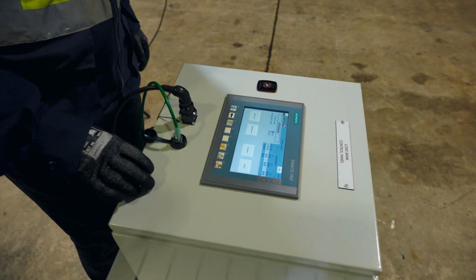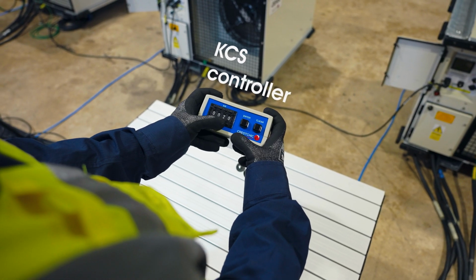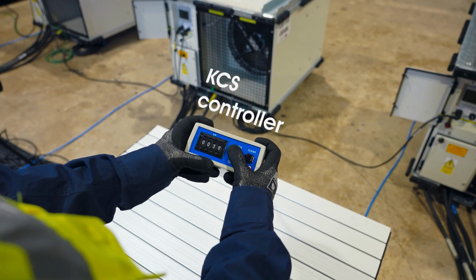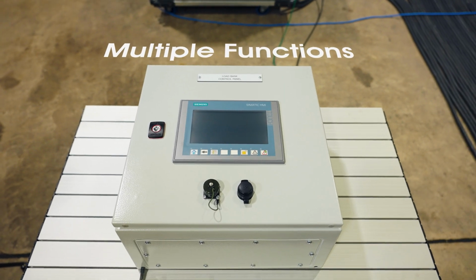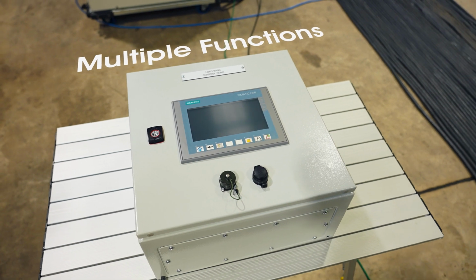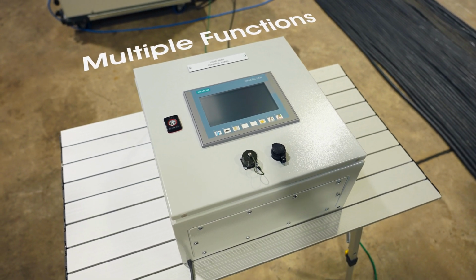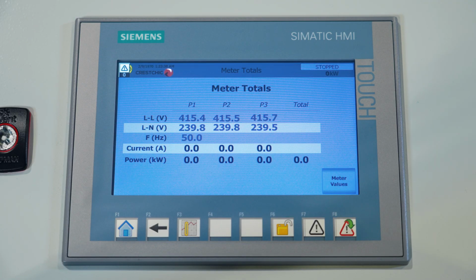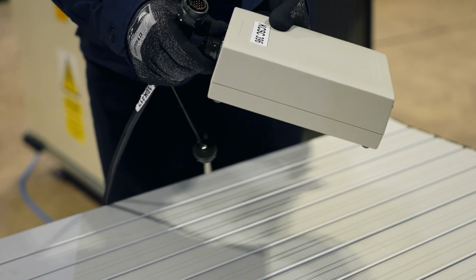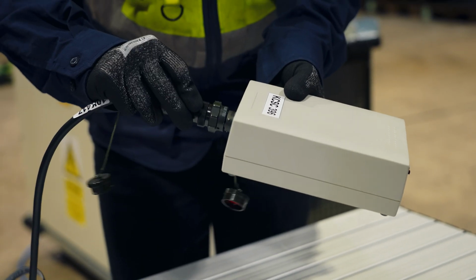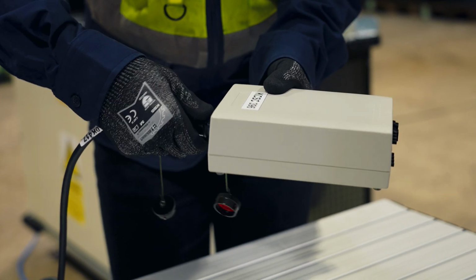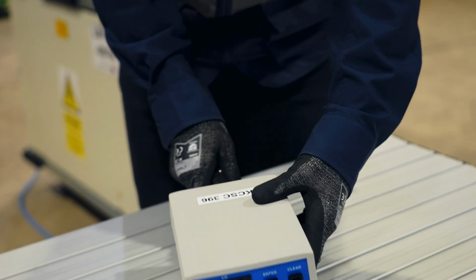Depending on the application the load banks are being used in, will depend on which controller is best suited for controlling the load banks. The KCS controller is a very straightforward method of applying loads. The digital controller has more functions, including being able to automatically perform load tests of various loads for set amounts of time, with instrumentation viewable from each load bank as well as the total from all load banks being used. When using the KCS controller, the load banks can be connected together and be controlled from one controller, or the load banks can have a controller for each one.